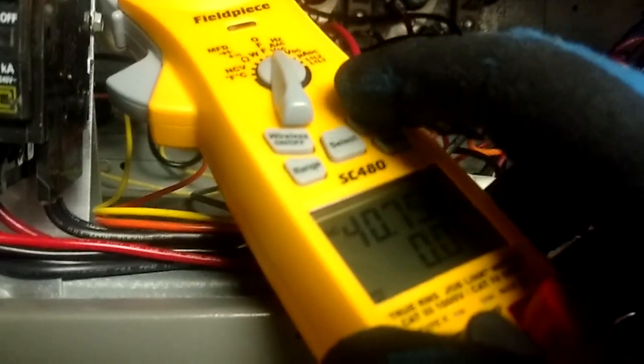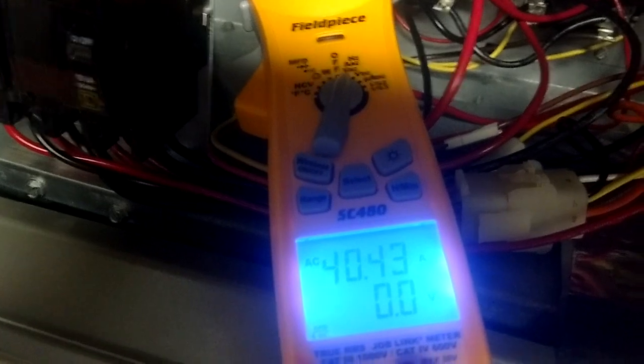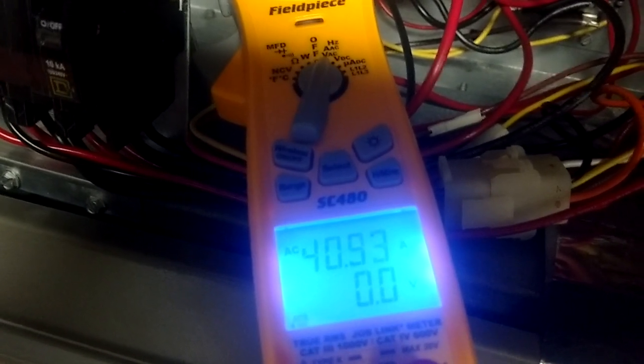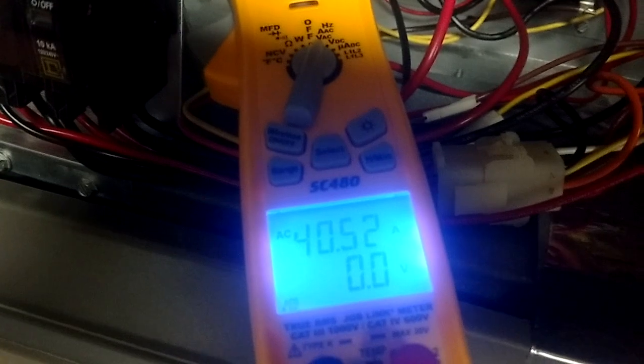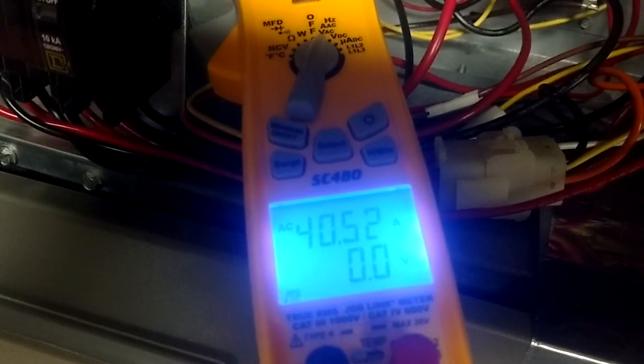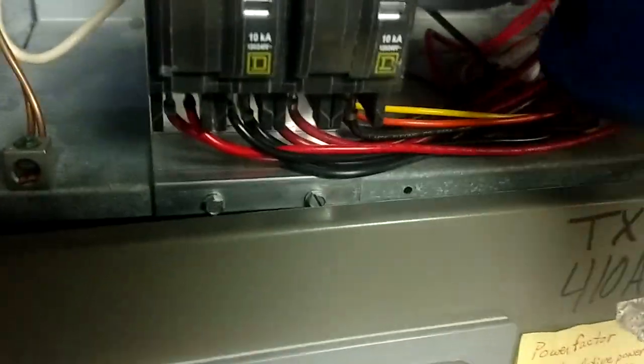So what we're going to do right now, we're going to go ahead and verify our heaters. And we've got our amps turned on there. And you can see that we have 40 amps. So that's two heaters running about 20 amps apiece. So both of those heaters are on. And then if we come over here to this side and get in there, you can see that we have 20 amps there, if you can see that. And we've got one heater on there.